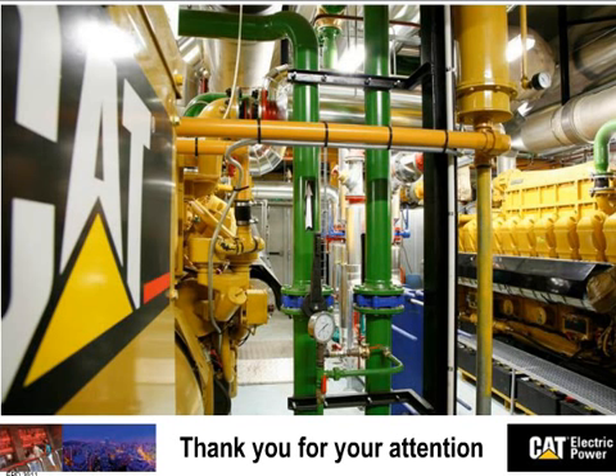On all our biogas generator sets, the jacket water temperature is elevated to combat the aggression of sulfur and contaminants from the gas, and they all run with elevated jacket temperature at 110. So that's a good thing. It's not 127, but it's already 110. 110 C is, again, that's 230 F. Good, thank you.